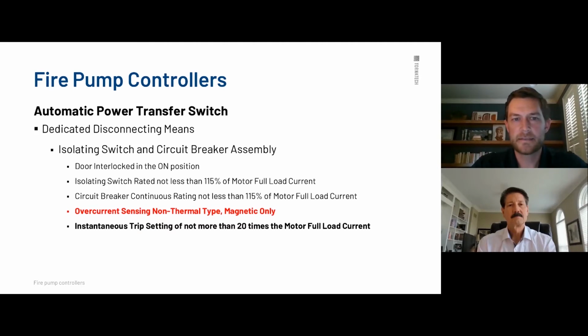It's got a dedicated disconnecting means, so it has its own isolation switch and circuit breaker assembly. Basically, it's somewhat of a mirror of what you see on the normal power side. It's the same isolating switch and circuit breaker assembly, rated for the same types of loads that you get on the normal power side, and it's also a non-thermal type magnetic only circuit breaker, just like it is on the normal power side.